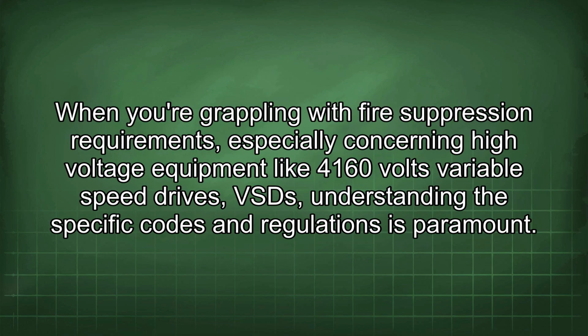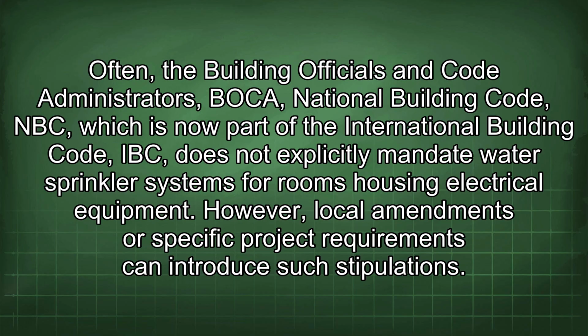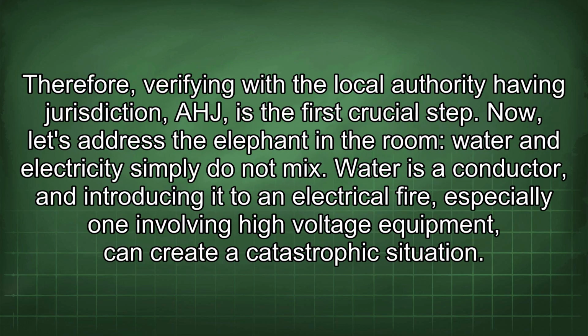When you're grappling with fire suppression requirements, especially concerning high voltage equipment like 4,160 volts variable speed drives, VSDs, understanding the specific codes and regulations is paramount. Often, the Building Officials and Code Administrators, BOCA, National Building Code, NBC, which is now part of the International Building Code, IBC, does not explicitly mandate water sprinkler systems for rooms housing electrical equipment. However, local amendments or specific project requirements can introduce such stipulations. Therefore, verifying with the local authority having jurisdiction, AHJ, is the first crucial step.